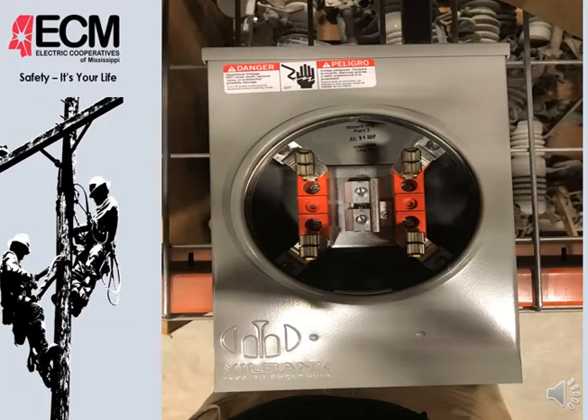He's doing this under the assumption that when we get there, we're going to do our job. We're going to pull the cover off this meter base, do our meter base inspection, and we're going to find this. In such a case where this has happened and you don't do the inspection and don't find this, and we energize this meter base, you're going to have a phase-to-phase, phase-to-ground fault. It's going to be a problem.